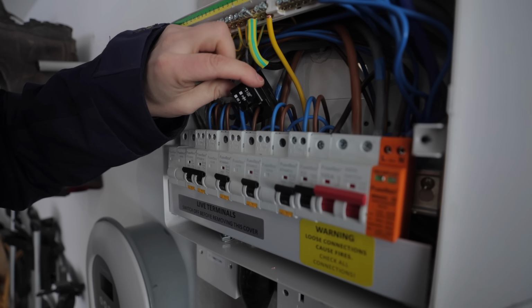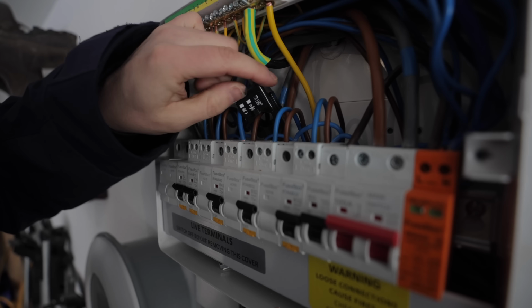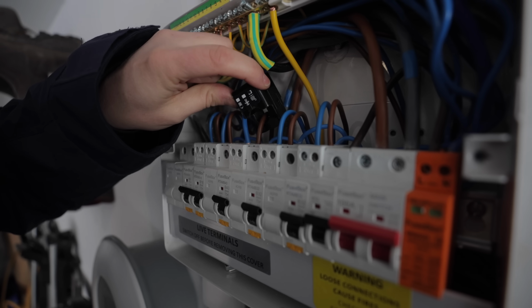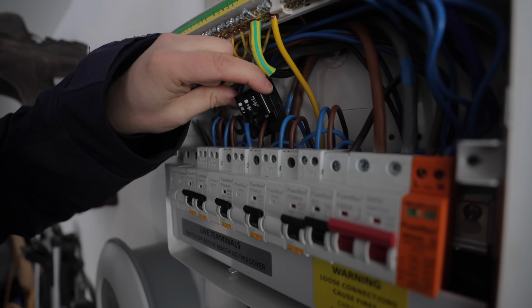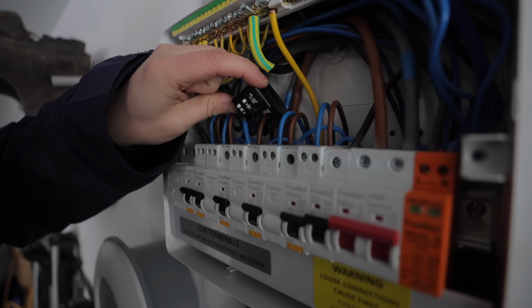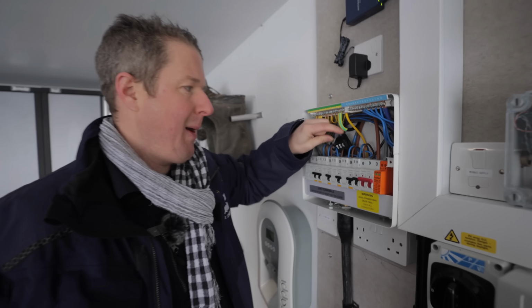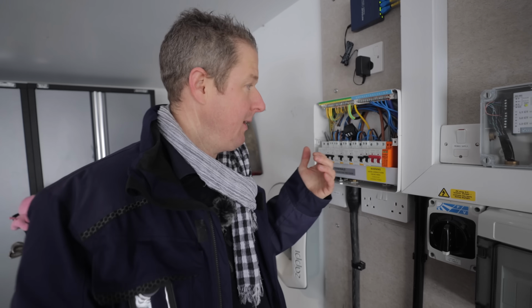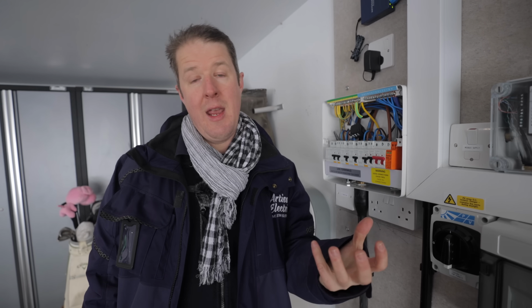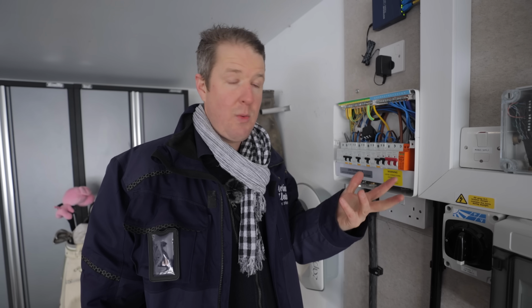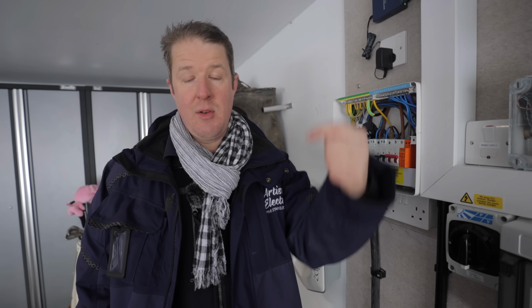It's a little magnetic coil that wraps around the wire, in this case the wire coming in from the solar PV system, effectively measuring how much power the solar PV system is generating. We've got another one of these CTs on the main supply tail to the property, measuring how much the whole house is using, importing or exporting. And we've got a third CT around the existing solar PV system in the house, measuring how much that system is generating.